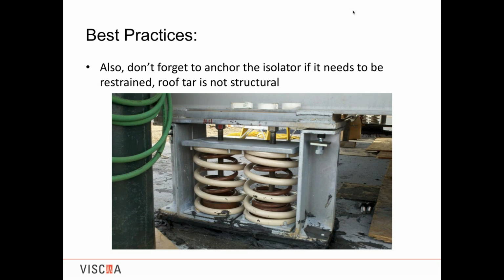The pictures will tell us everything if you're having a vibration problem. And the vibration problem here is the spacer is removed, and it looks like there's a bent bolt, so the contractor tried to do something. I would have no idea what he tried to do. But more importantly, for an outdoor application, the isolator is going to come with holes in its plate to bolt down to the building, so when the wind blows, the restrained isolator keeps the equipment in place.